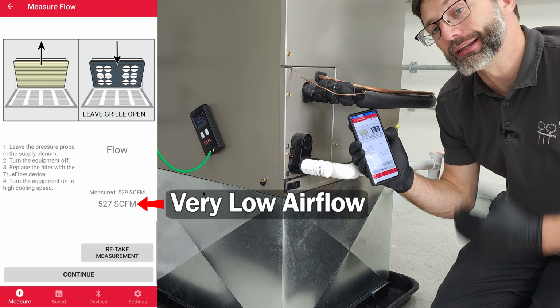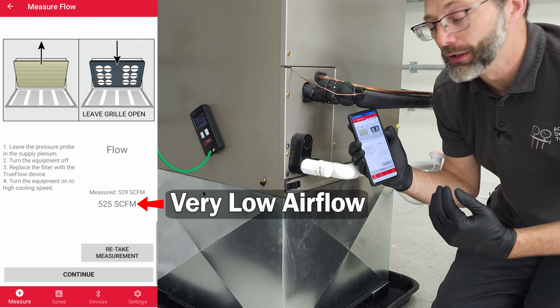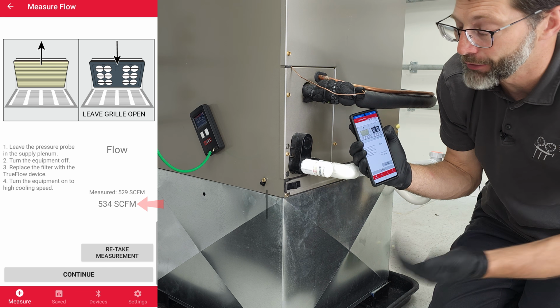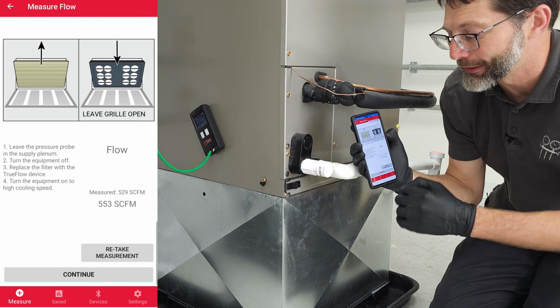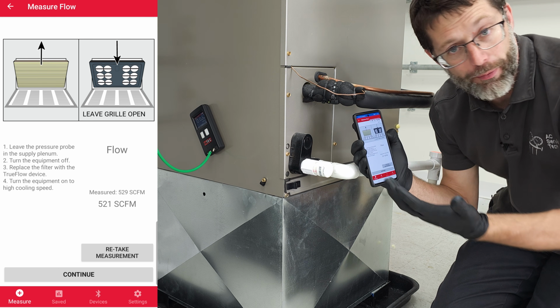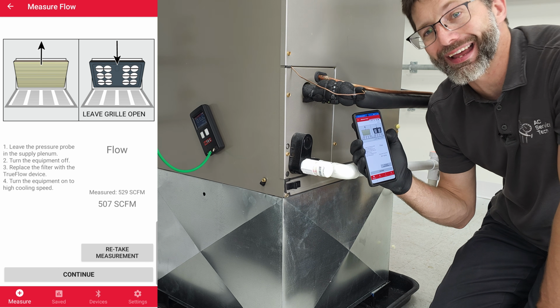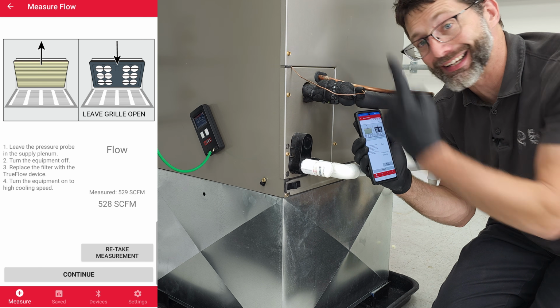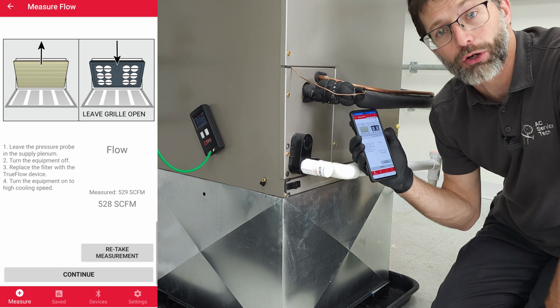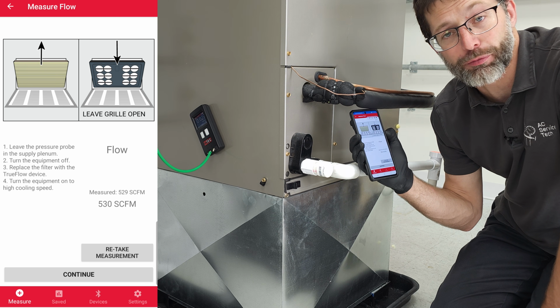So we want to find the airflow problem. So, you know, do we have an issue in the return or in the supply? And with this app, you can determine where the problem is. I already know where that is, and that's with the airflow settings in this air handler. So we're going to go up to the electrical cabinet and make our adjustments, and then we're going to measure our airflow again.